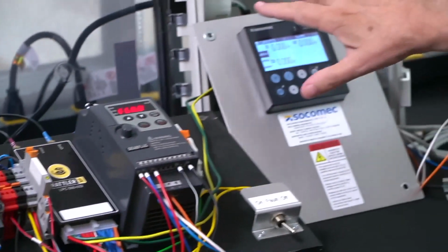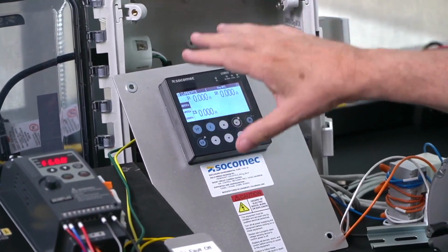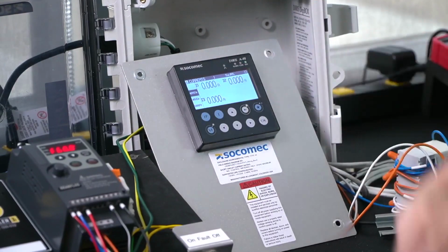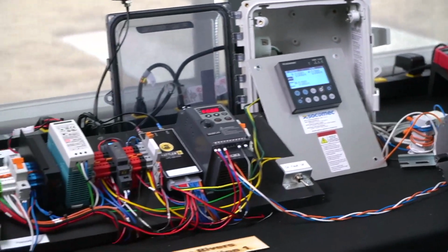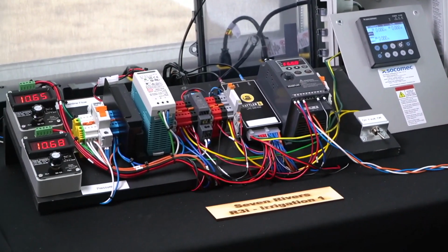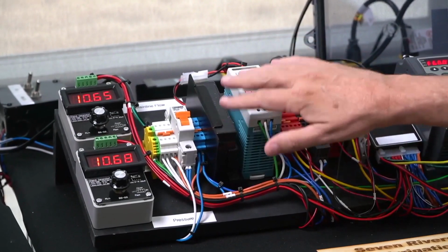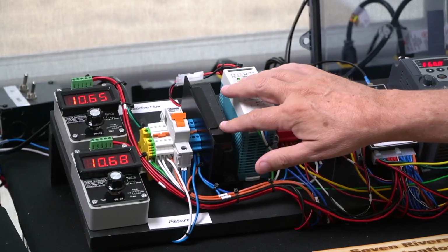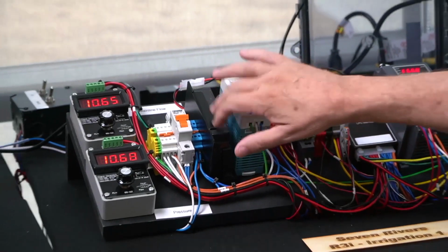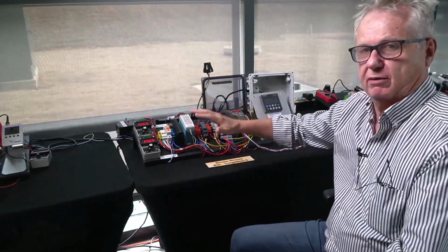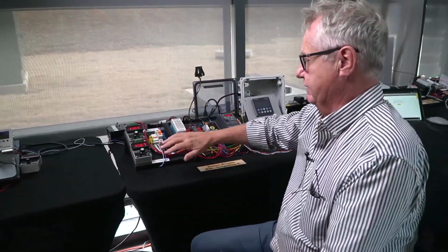We've got a Socomec meter, which measures the current and other characteristics. For this instance, we're just monitoring the system amperage from the Socomec meter. We've got a last gasp battery and power supply, which keeps the whole system up and running. So when you have a power failure in the field, this battery keeps the Rattler running and reports and alarms that there's been a power failure in the field.